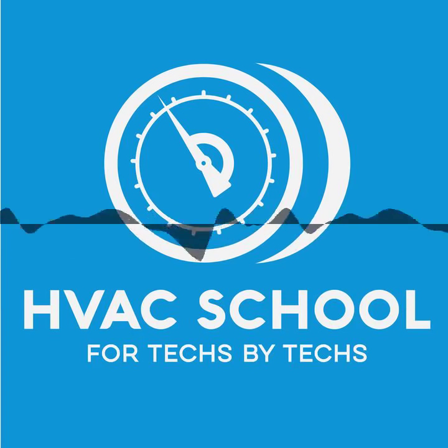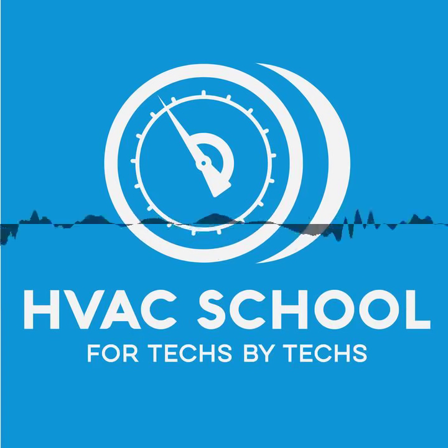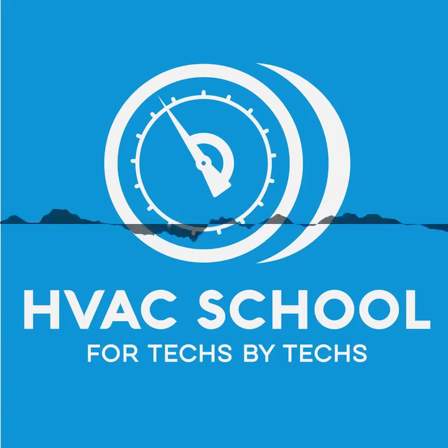A common one: the technician will say, like I just said, I don't have voltage at my contactor. Okay, well, where are you reading between? "Well, I've got nothing between yellow and red." Okay. Now, most of you know, if you've done this for a while, that that's not how you do that. You either read across the contactor coil itself, which is my preferred place to start, or you could read between yellow and blue coming in. That would tell you something, blue being common on the opposite side of the circuit from red.